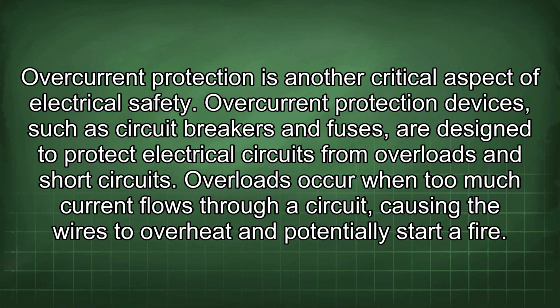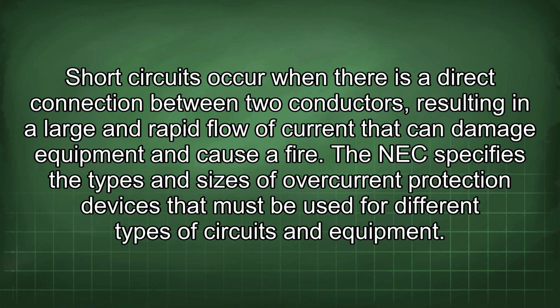Overcurrent protection devices, such as circuit breakers and fuses, are designed to protect electrical circuits from overloads and short circuits. Overloads occur when too much current flows through a circuit, causing the wires to overheat and potentially start a fire. Short circuits occur when there is a direct connection between two conductors, resulting in a large and rapid flow of current that can damage equipment and cause a fire.